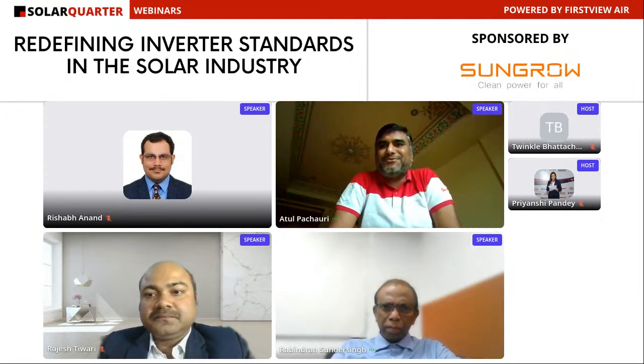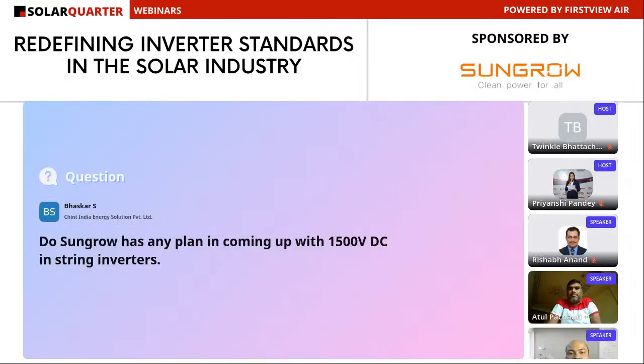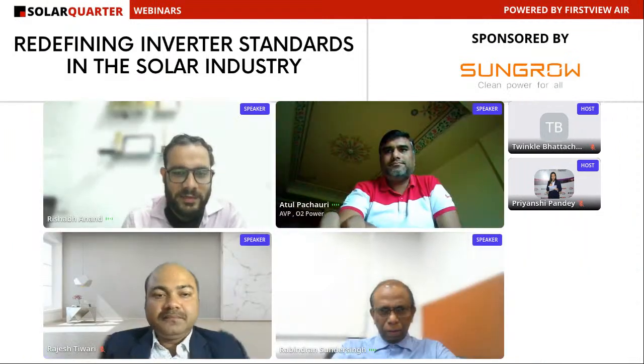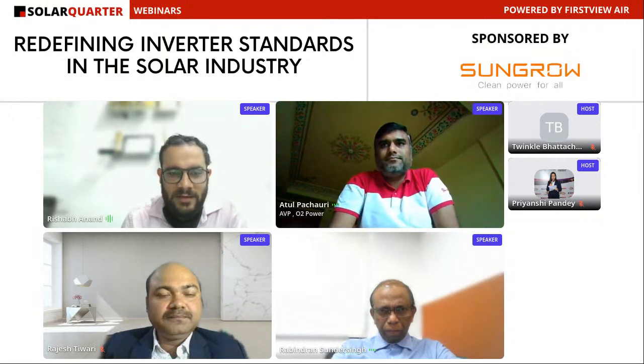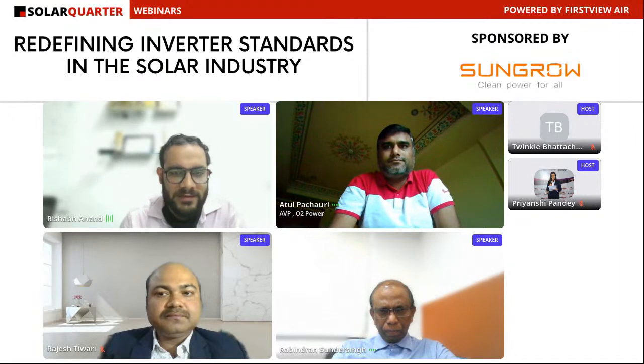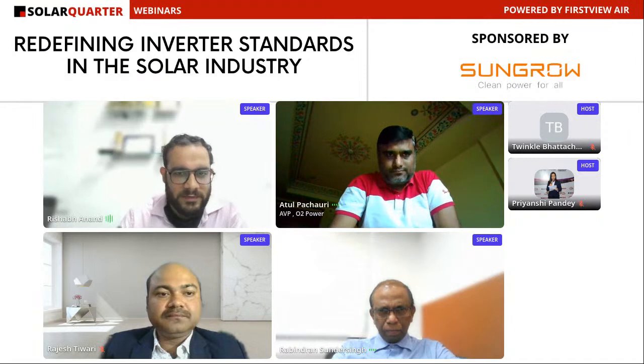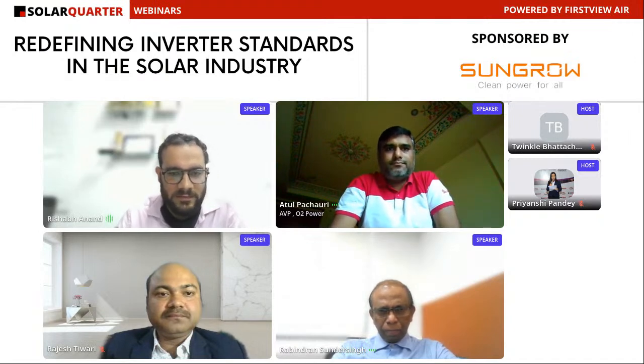Another question from Mr. Bhaskar S, directly to Sungrow: does Sungrow have any plan to come up with 1500 volt DC string inverters? Sir, we already have 1500 volt DC string inverters for the last 5 years. Earlier it used to be the SG125HV, a single MPPT string inverter. After that we had the SG 250 HX IN and IN-20, and the recent model is the SG 320 HX. All these models are compatible and rated for 1500 volt DC systems.